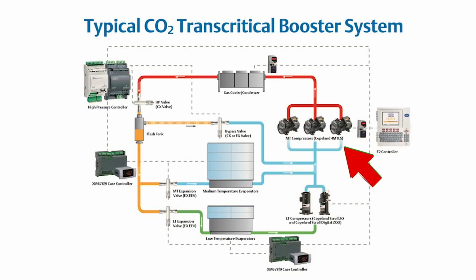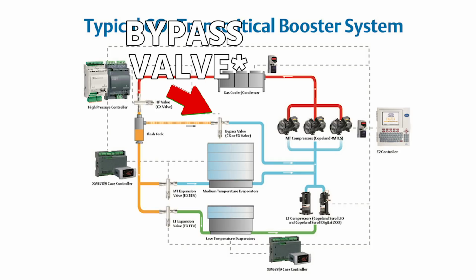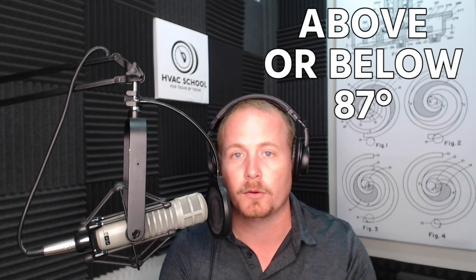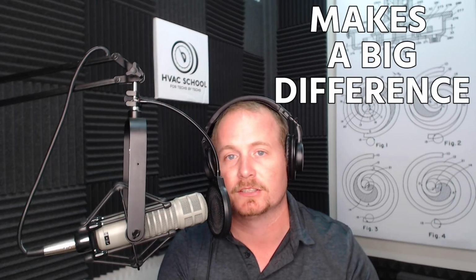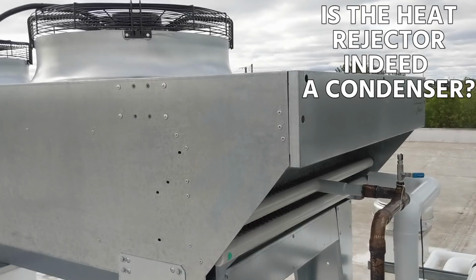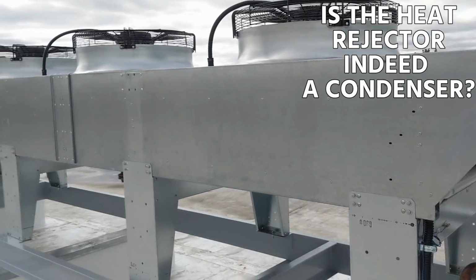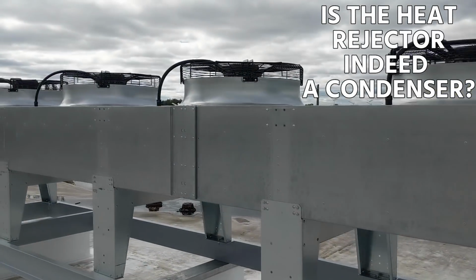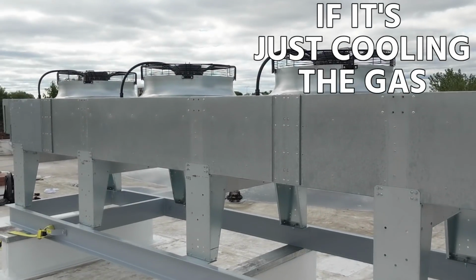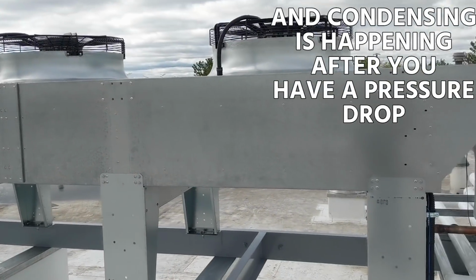And then those medium temp compressors, those are what discharge into the gas cooler / condenser, depending on the conditions. Then they go into that high pressure valve, the flash tank, bypass valve, and then your expansion valves back. So depending on your conditions, whether or not you are above or below 87 degrees, that's going to make a big difference in how those valves function and whether or not that heat rejector up on the roof that we would normally call a condenser is indeed a condenser, where it's condensing from vapor to liquid, or if it's just cooling the gas and then the condensing is happening after you have that pressure drop.